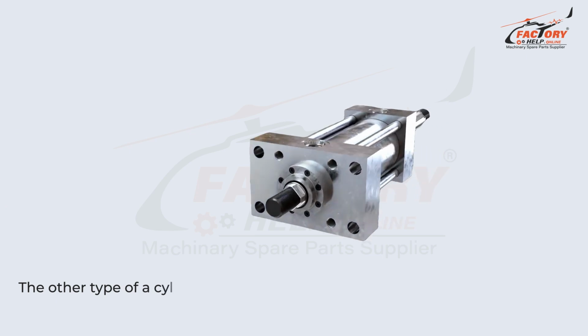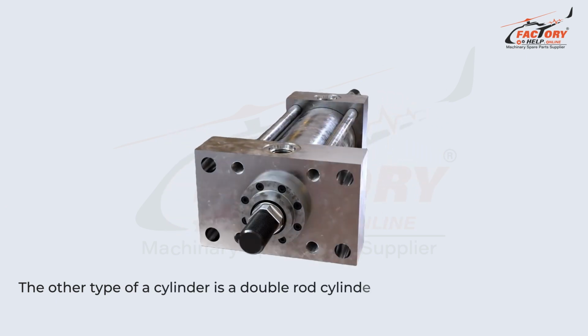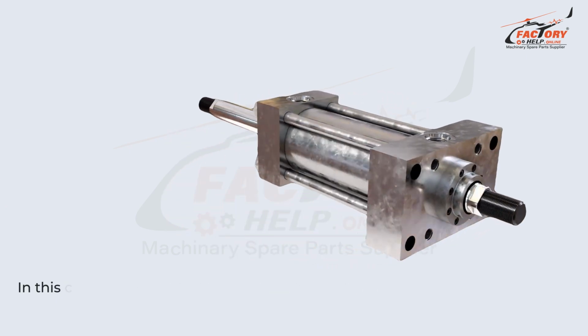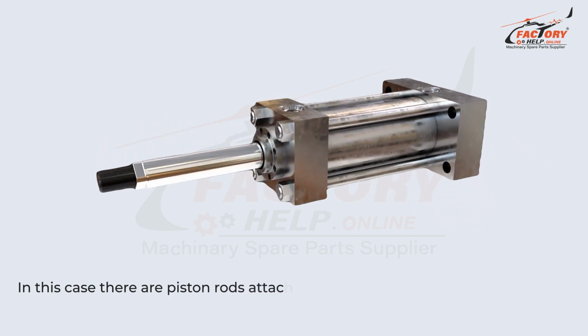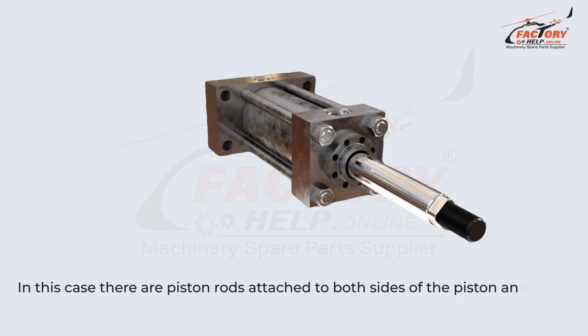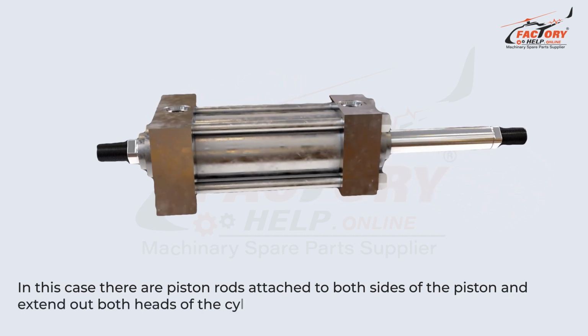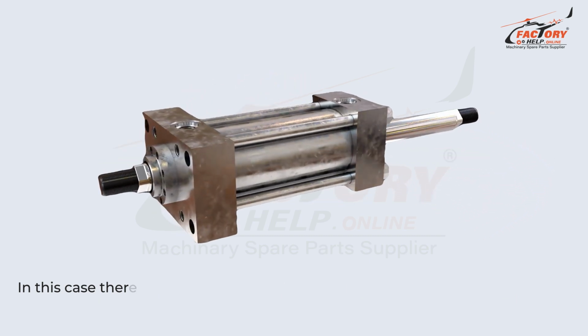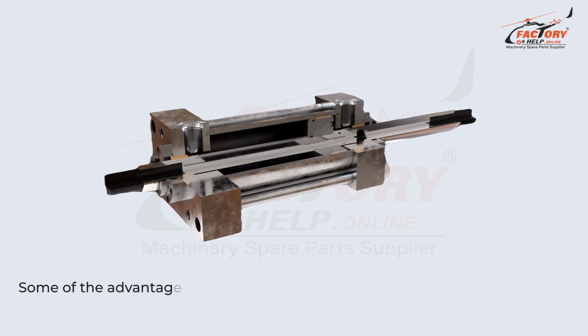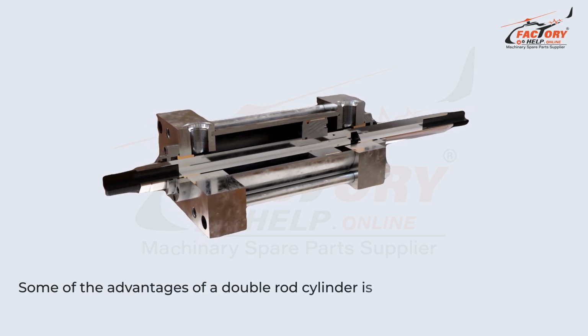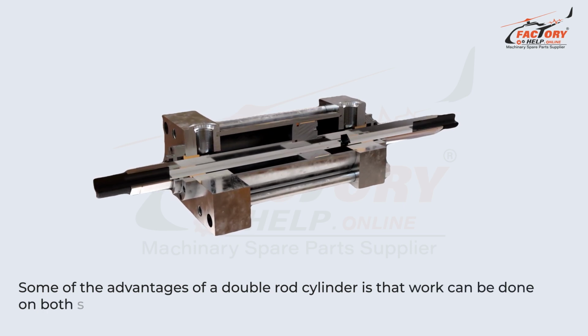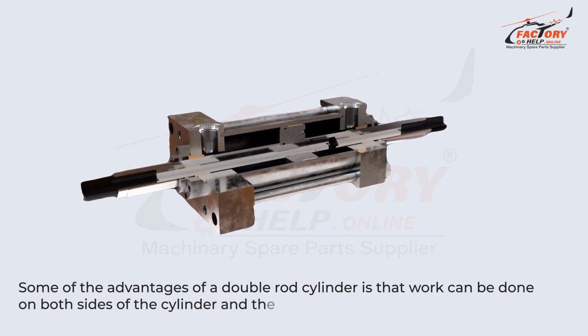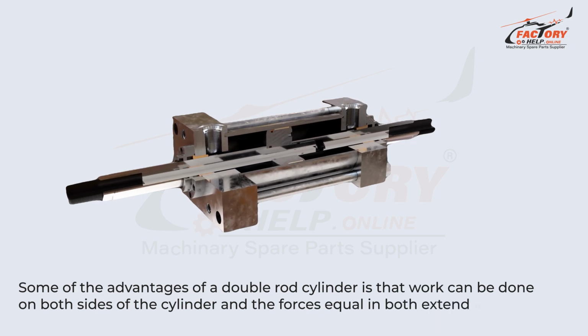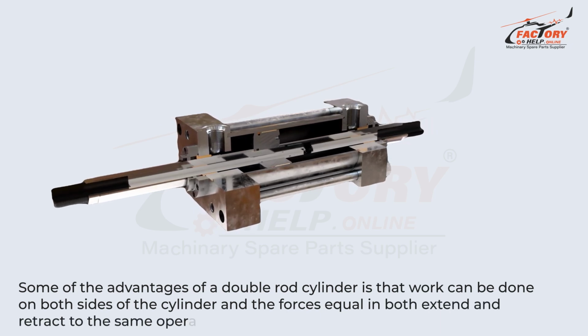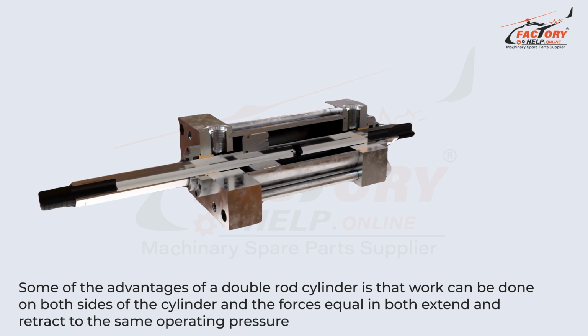The other type of cylinder is a double rod cylinder. In this case, there are piston rods attached to both sides of the piston and extending out both heads of the cylinder. Some of the advantages of a double rod cylinder are that work can be done on both sides of the cylinder and the force is equal in both extend and retract at the same operating pressure.